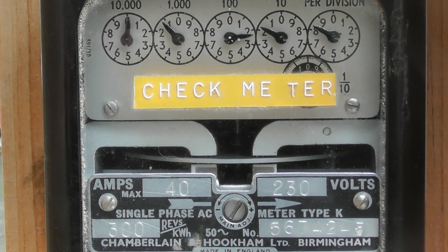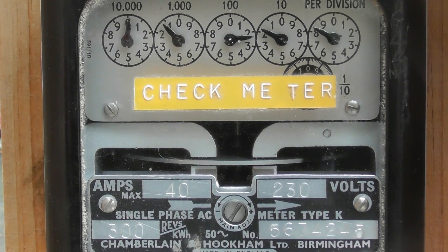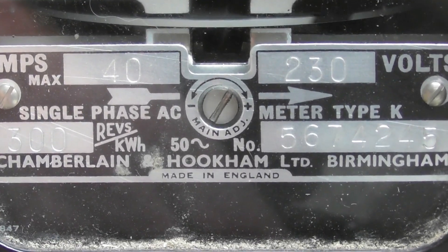Here we have a Chamberlain and Hookham meter made in Birmingham, United Kingdom. Meter was built in 1956. The disc constant is 300 revolutions per kilowatt hour. Meter is rated at 40 ampere maximum for a supply voltage of 230 volts.